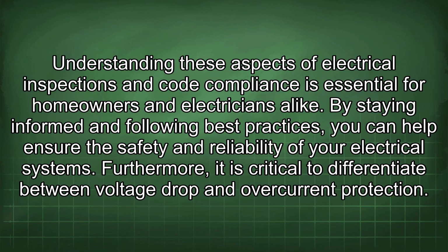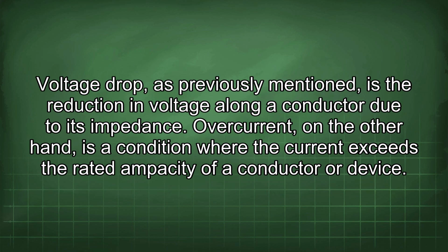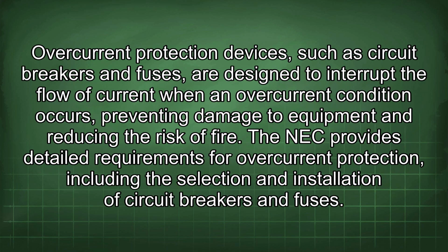Furthermore, it is critical to differentiate between voltage drop and overcurrent protection. Voltage drop, as previously mentioned, is the reduction in voltage along a conductor due to its impedance. Overcurrent, on the other hand, is a condition where the current exceeds the rated ampacity of a conductor or device. Overcurrent protection devices, such as circuit breakers and fuses, are designed to interrupt the flow of current when an overcurrent condition occurs, preventing damage to equipment and reducing the risk of fire.